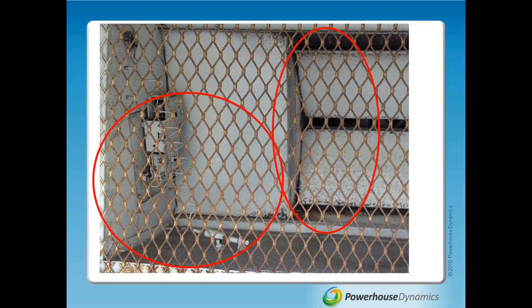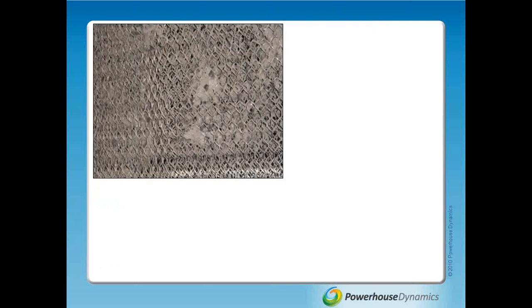The economizer is the number 1 fault for rooftop units. Making sure they're connected, they have properly placed temp sensors, and accurate damper positions are key. A clean economizer screen is also part of a well-functioning unit.